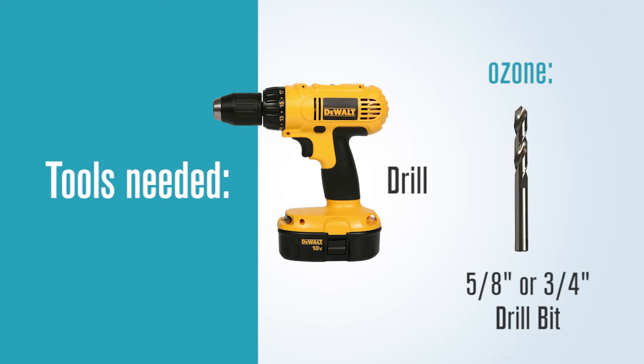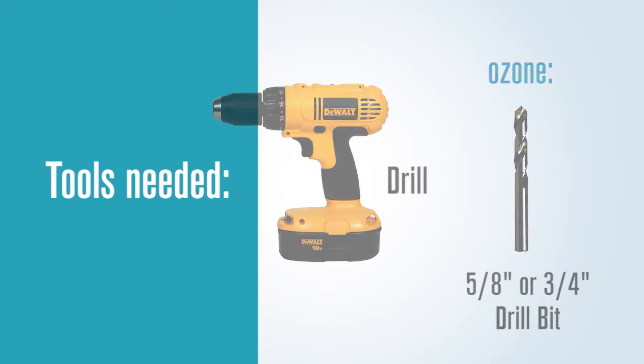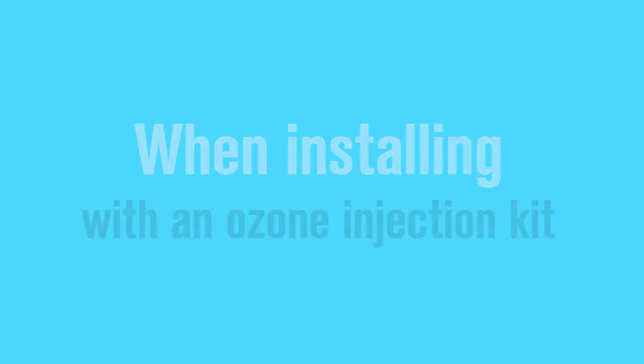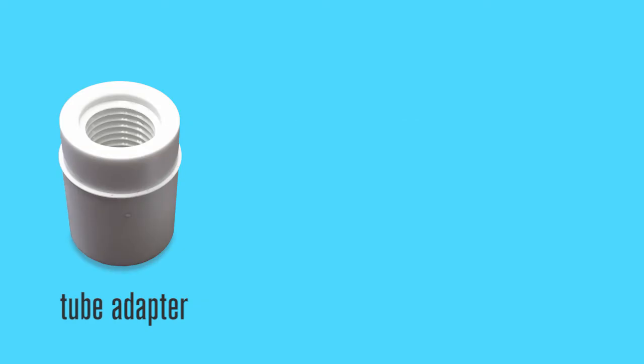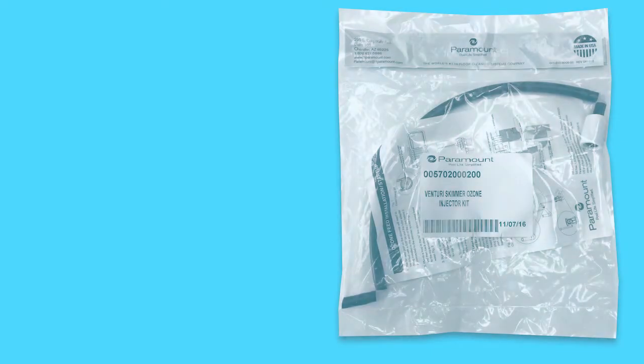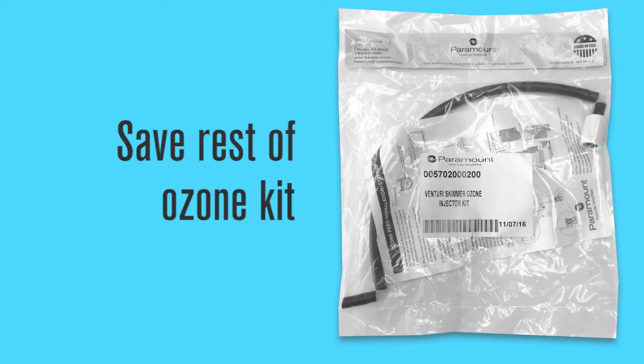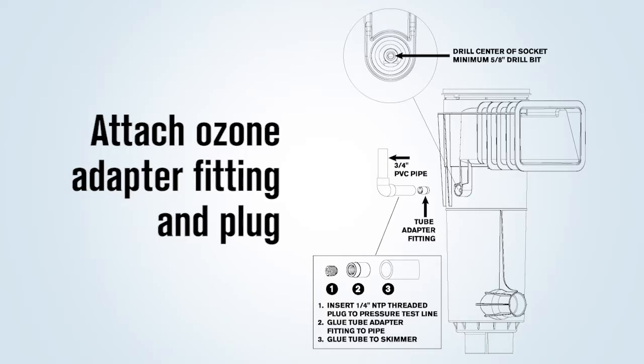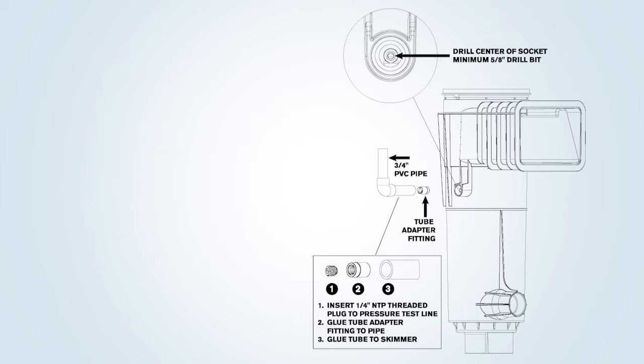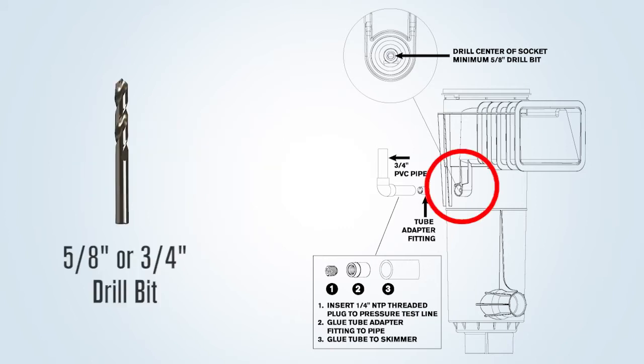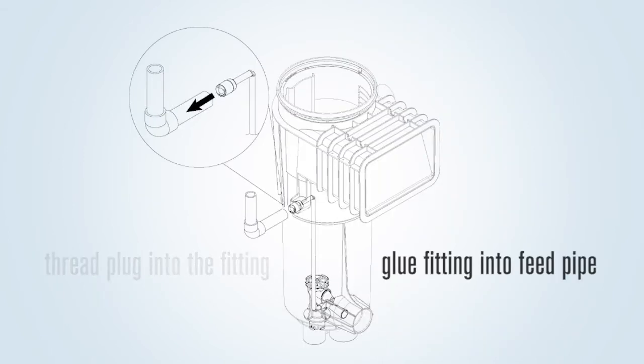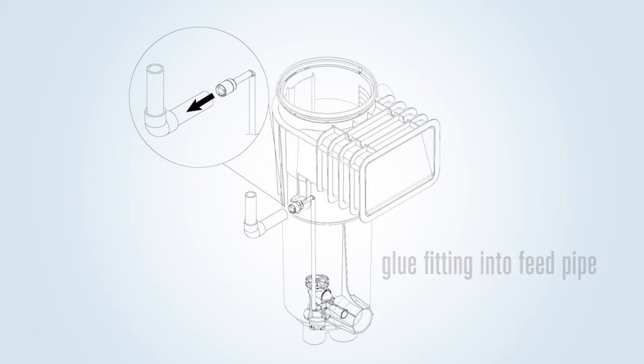When installed with an ozone injection kit, the tube adapter and the quarter inch NPT plug must be installed by the plumber. The remaining parts in the kit must be saved for the other phases of install. To attach the ozone adapter fitting and plug, drill out the three-quarter inch socket with a five-eighths to three-quarter inch drill bit for the feed line first. Then thread the plug into the fitting and glue the fitting into the three-quarter inch feed pipe. Then glue the pipe plug in first into the skimmer.